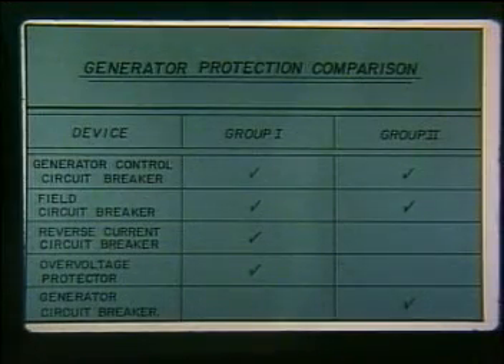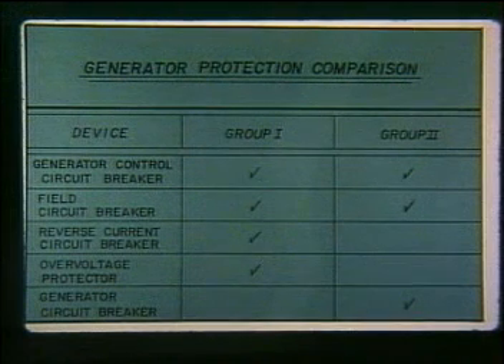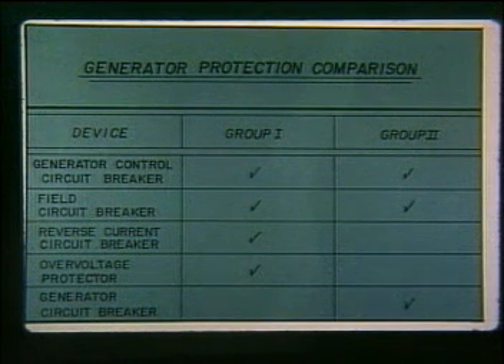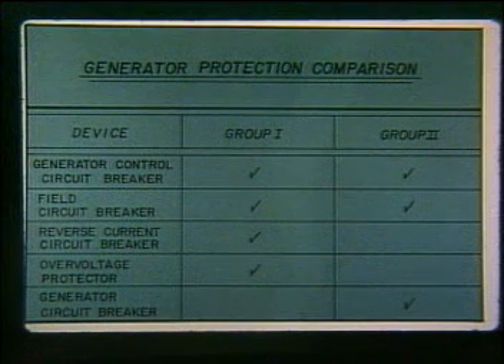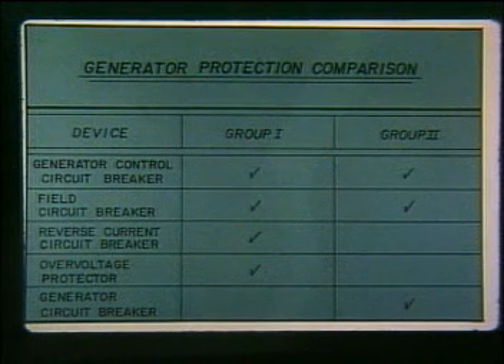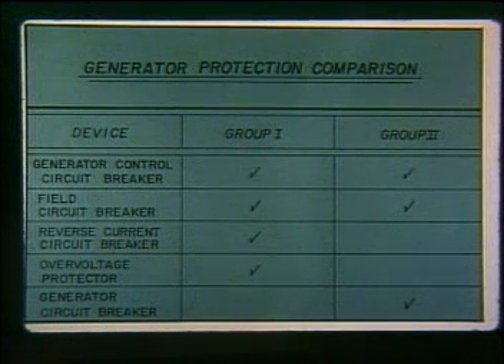In comparing the protective devices for the Group 1 and Group 2 systems, we find that the generator control circuit breakers and the generator field circuit breakers have the same protective function and physical location. The individual functions of the reverse current circuit breaker and the overvoltage protector in Group 1 aircraft have been combined in the generator circuit breaker in the Group 2 aircraft. In addition, the Group 2 generator circuit breaker in conjunction with the fault detector panel provides improved bus overvoltage protection, grounded generator feeder protection, and excessive overload protection for the generator.